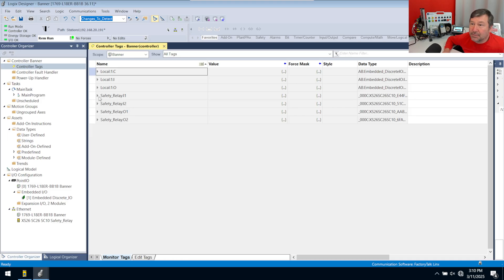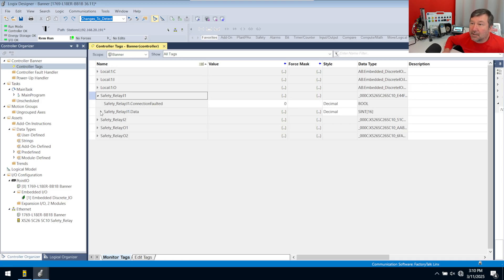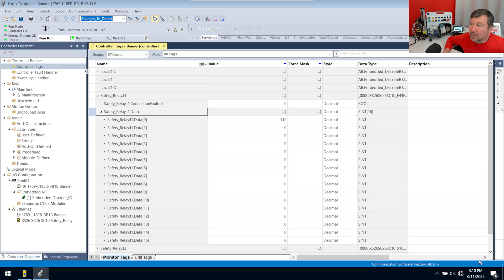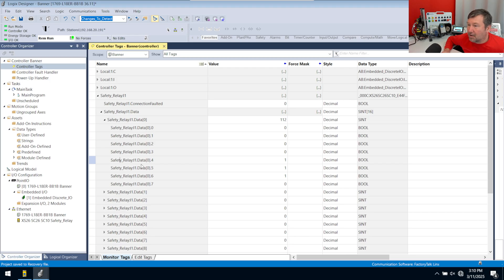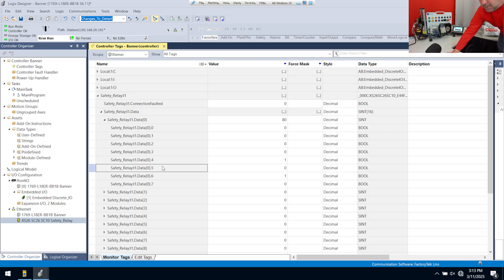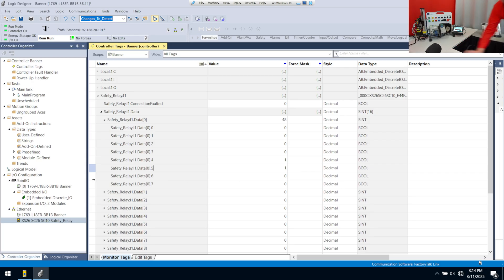We have Safety_Relay:I1 and I2. Inside I1, according to the mapping, I should have a few outputs — I have bits four, five, and six. I can dig a little closer: I open the safety gate and I lose bit five, I press the E-stop and I lose bit six, and I block the light curtain and I lose bit four.